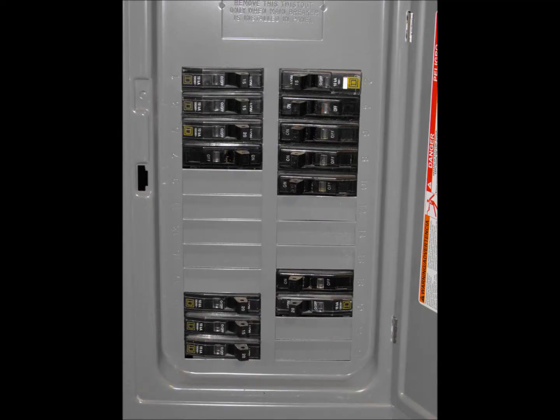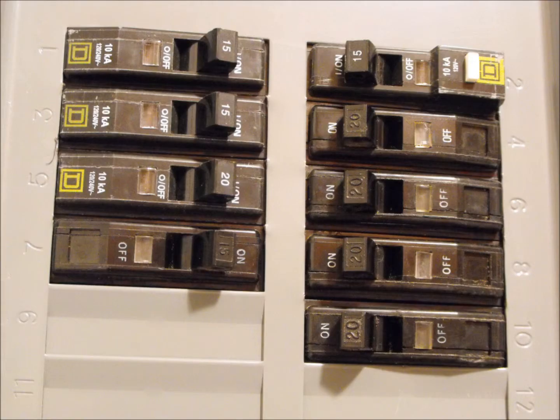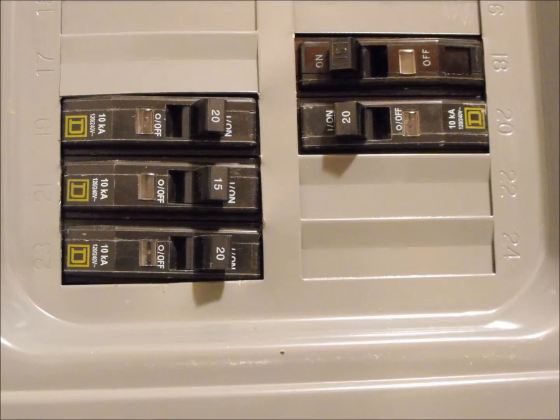There are several different types of circuit breakers. One type is made with a switch and a strip composed of two metals. This bimetallic strip will warp when heated because of its resistance to the current. If the current is above the rated value of the circuit breaker, the bimetallic strip will bend enough to open or trip the switch and stop the flow of current. Once the strip cools, it will return to its original shape, thus allowing the circuit breaker to be easily reset with the flip of a switch.